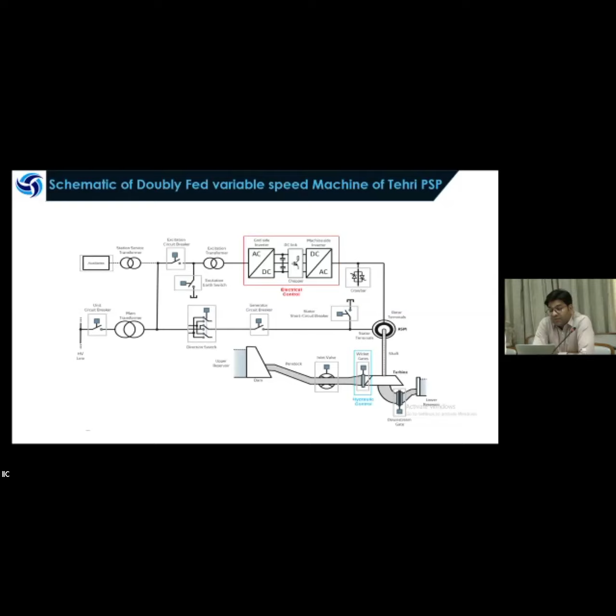The main transformer also feeds the voltage source inverter, which is a converter that first converts the AC into DC, then DC into AC, which is fed to the rotor three-phase windings provided with a crowbar for overvoltage protection. Both the voltage and frequency of the rotor can be adjusted by this voltage source inverter.